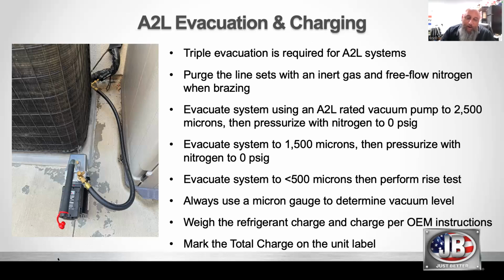Yeah, 29.9 inches of mercury is 500 microns. Yeah. 29.75 inches of mercury is 4,000 microns. There you go. That's less than the width of the needle on most analog gauges. So yeah, they're just 2 different scales. It's like we need to measure in inches, not yards. Absolutely.